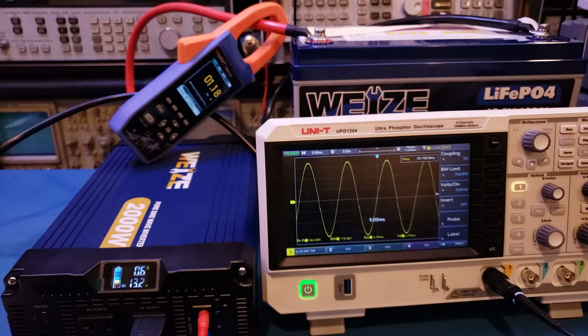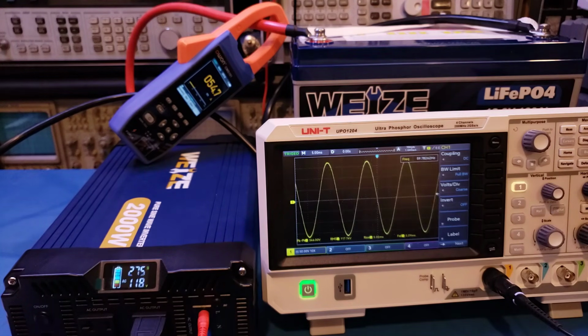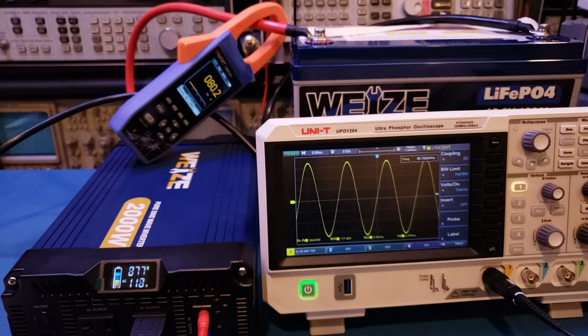So let's actually increase the load here. Right now we're at maximum rated power for the inverter. Let's keep increasing to see if we can push it any higher. The distortion does look a little worse now, and you can see it's no longer symmetric. Let's increase the output a bit more since we should have some margin on the inverter. Right now we're continuously outputting over 2100 watts.